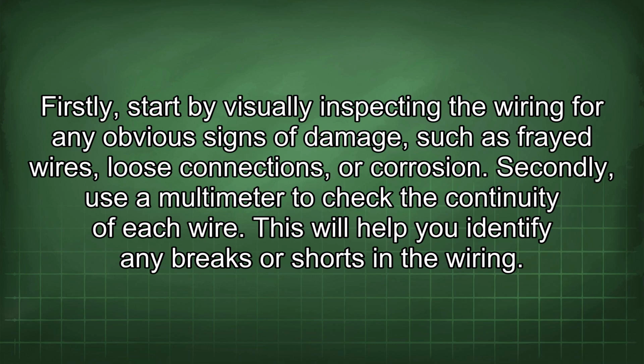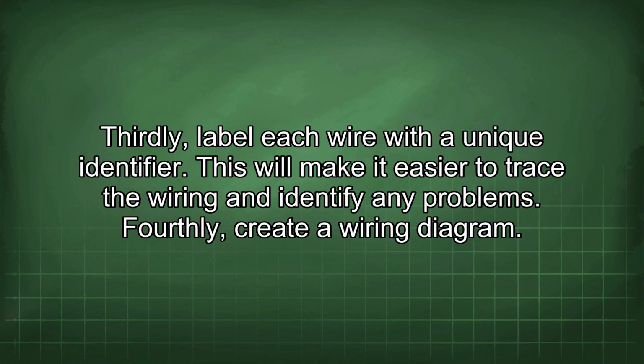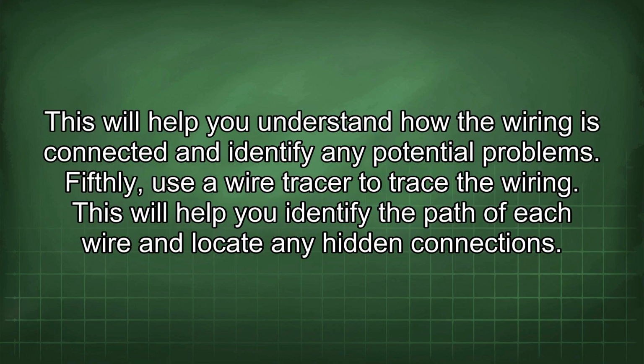Firstly, start by visually inspecting the wiring for any obvious signs of damage, such as frayed wires, loose connections, or corrosion. Secondly, use a multimeter to check the continuity of each wire. This will help you identify any breaks or shorts in the wiring. Thirdly, label each wire with a unique identifier. This will make it easier to trace the wiring and identify any problems. Fourthly, create a wiring diagram. This will help you understand how the wiring is connected and identify any potential problems.